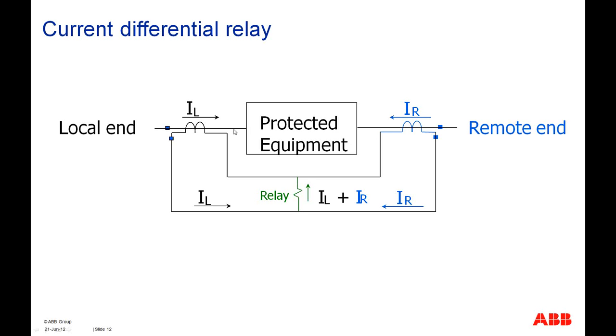And this is the protected object. That protected object can be a transmission line in the case of line differential protection, or in the case of other protected equipment like a transformer or anything like that. So that would be the protected object, but basically the idea of differential protection is the same. So this would be the ideal situation, when these CTs actually have ideal characteristics.